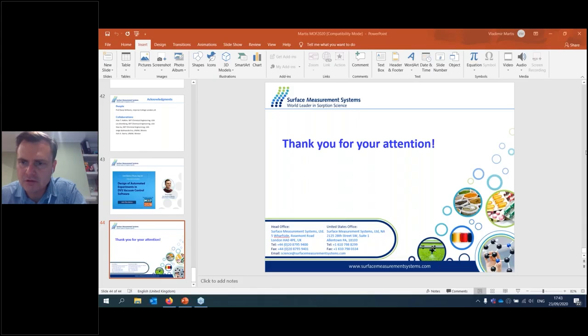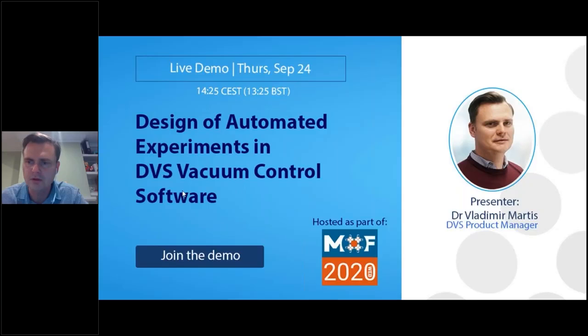Okay, so we have a question from Victoria Kulaova. Her question is, does post-adsorption H2O/CO2 measurement using DVS require first pre-saturation of the sample with water vapor and then CO2 adsorption? That's correct, you actually got it right. In this talk, I showed two examples. In my last example, in the static mode, as you described, I need a pre-saturation with water vapor, and then I introduce the CO2 on top of it.